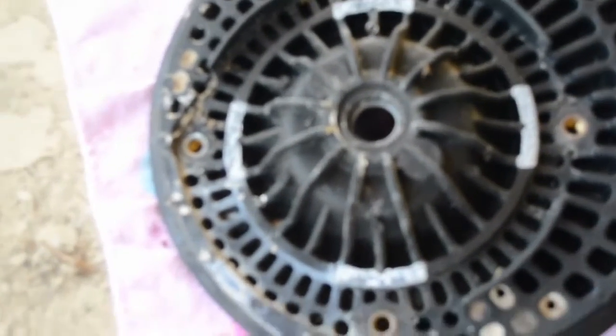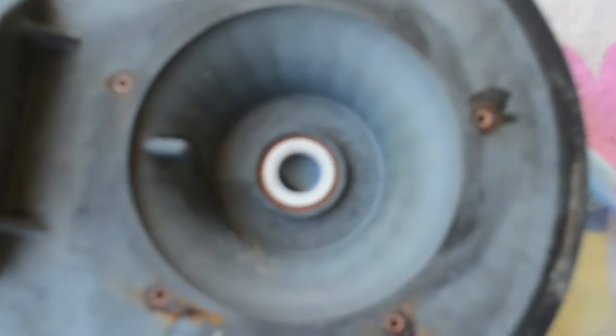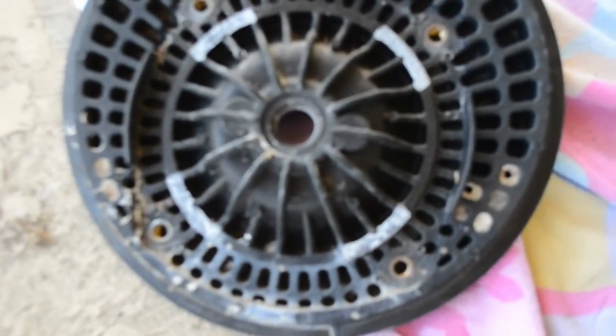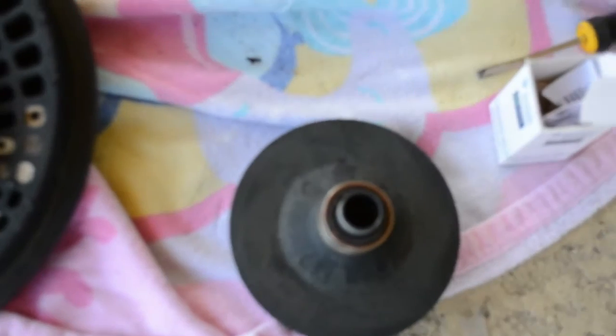The second portion — right in here, let me flip it over so you can see a little better — this little threaded piece in here is the second half of the shaft seal. In order to get this out, I'm going to take a flat-head screwdriver to the back, hit the back end, and pop it out. Really important: before you take these off, note the orientation that the current ones are in, so you don't put them on backwards.